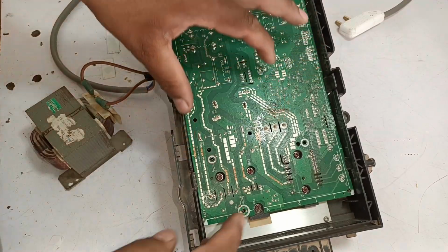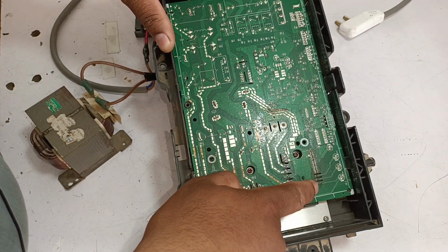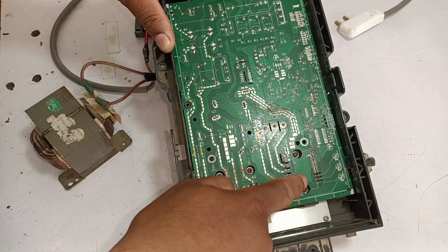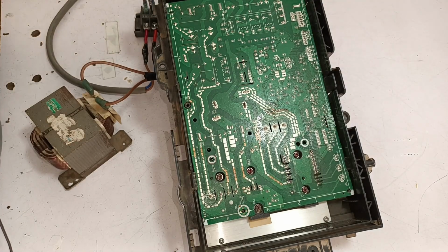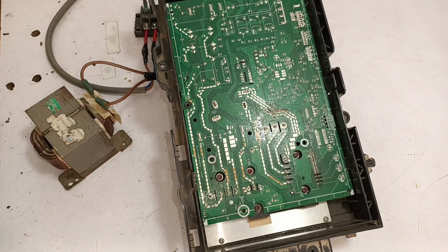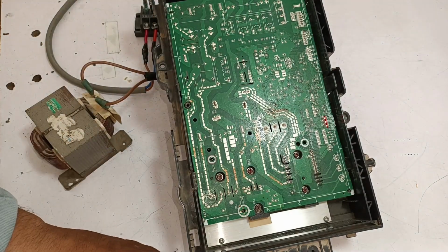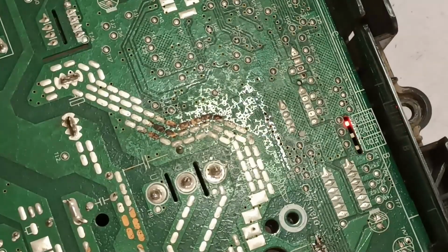Now that I've replaced the IPM, I mounted it with the heatsink and soldered it properly. This way, there is no gap between the heatsink and the IPM, which helps reduce the chances of the IPM overheating. After connecting the power and completing the wiring, I checked the system again to see if there was any change. However, the lights are still turning on in the same way, and after about 10 to 12 seconds, the system turns on. The LEDs 1 and 2 are continuously blinking, which indicates an F1 error. This suggests that the issue persists despite changing the IPM.